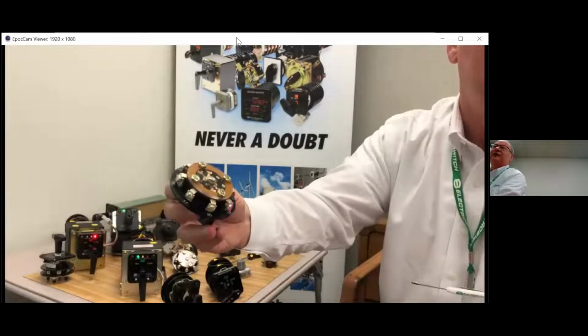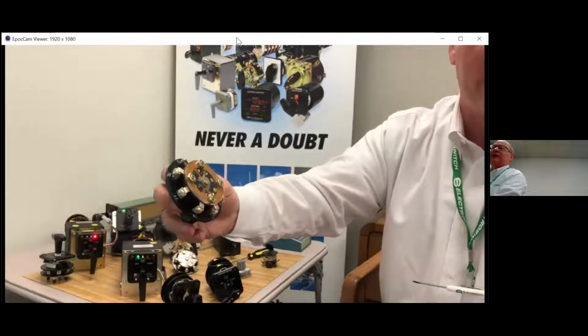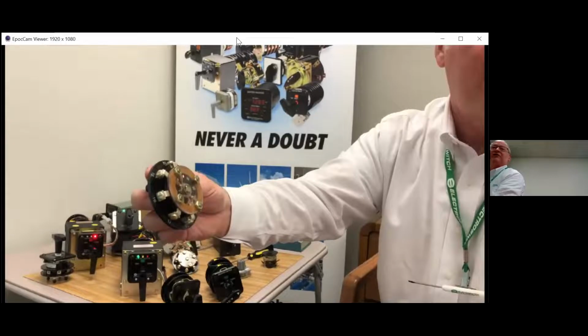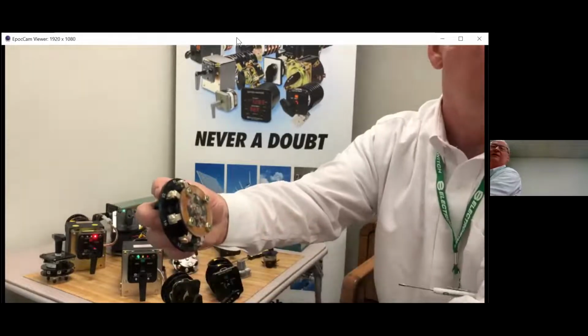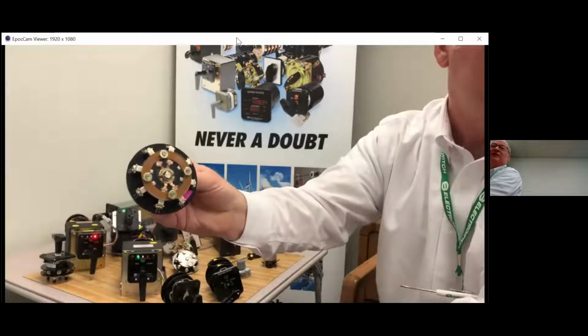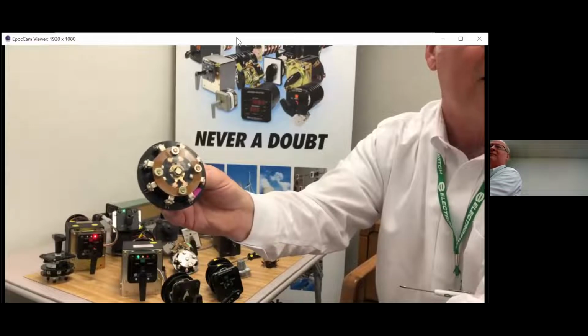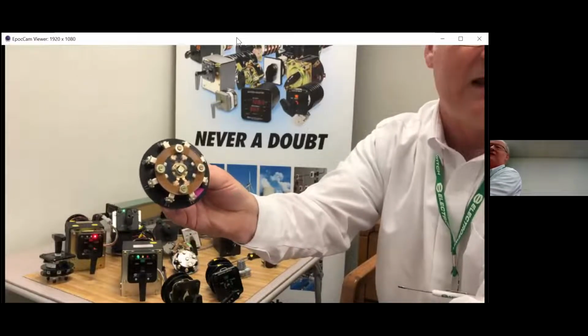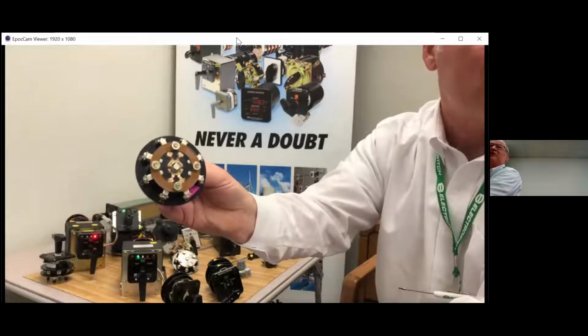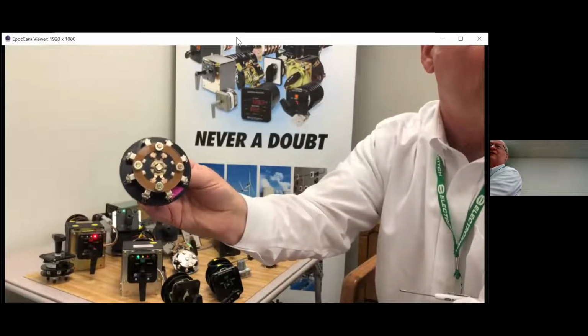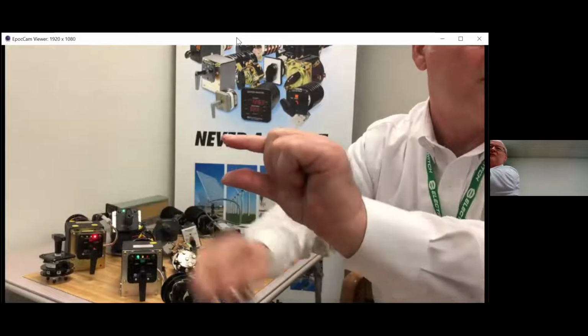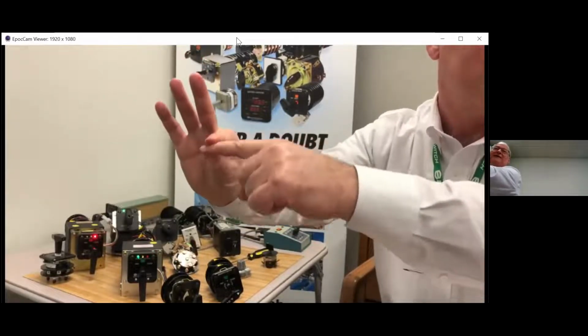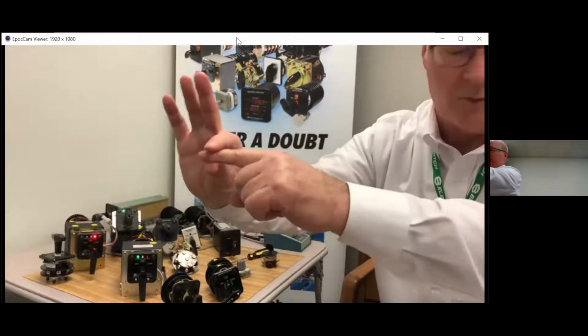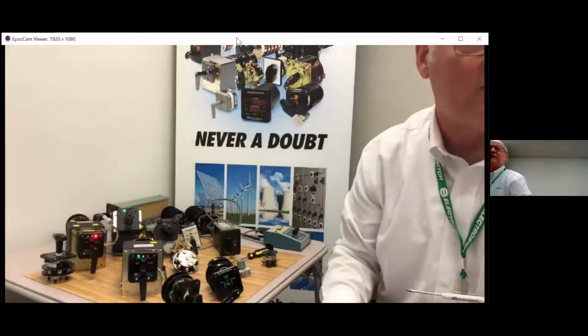And a lot of these switches are used in the military and the utility market. One of the key features of this switch is because I have a double wiping blade, a double wiping circuit, it's considered bounce proof. And that's one of the things that the military likes in their equipment, especially in their Navy ships, where there's a lot of vibration, where when there's a secure contact made, even if it's bouncing around, it's still going to have an open and close between the two blades here concept. So if I'm bouncing up and down, I'm still looking at solid contact on either side of the movable blade. So it's got that knife switch action that we like to have in a circuit.